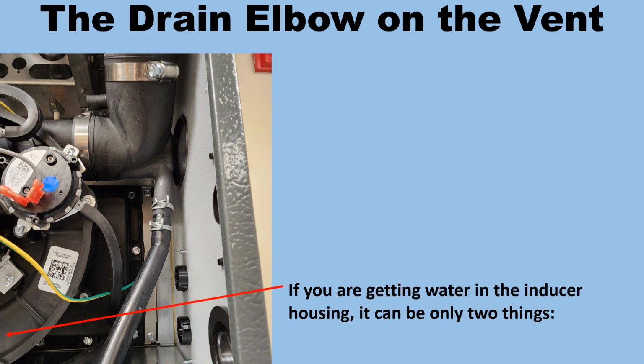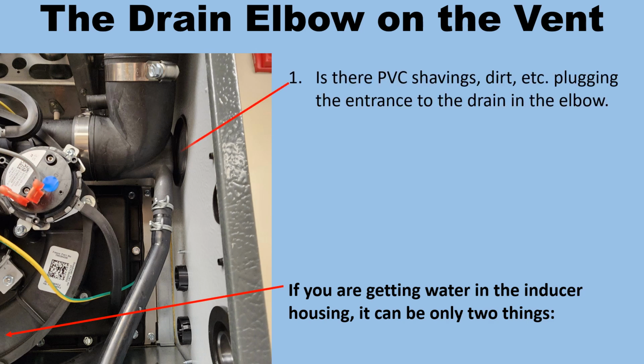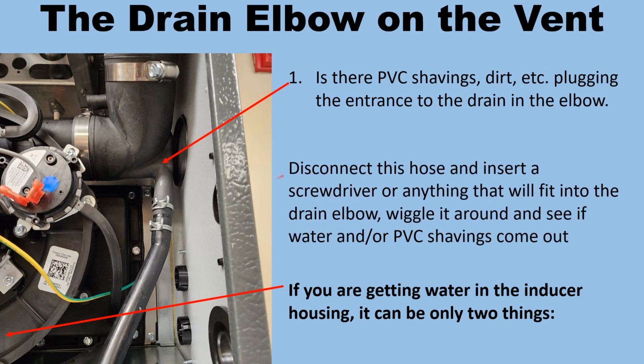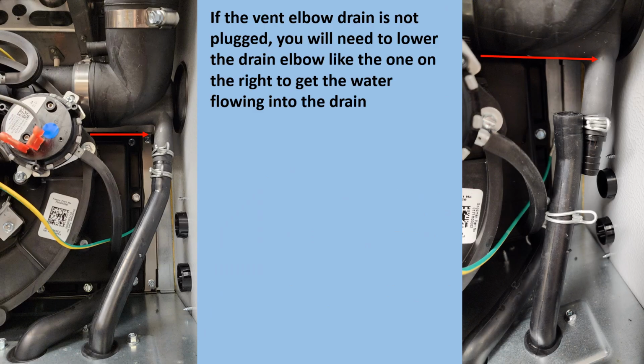If you're getting water in the inducer housing, it can only be two things. Is there PVC shavings, dirt, etc., plugging the entrance to the drain in the elbow? Disconnect this hose and insert a screwdriver or anything that will fit into the drain elbow. Wiggle it around and see if water and or PVC shavings come out. If the vent elbow drain is not plugged, you will need to lower the drain elbow like the one on the right to get the water flowing into the drain.